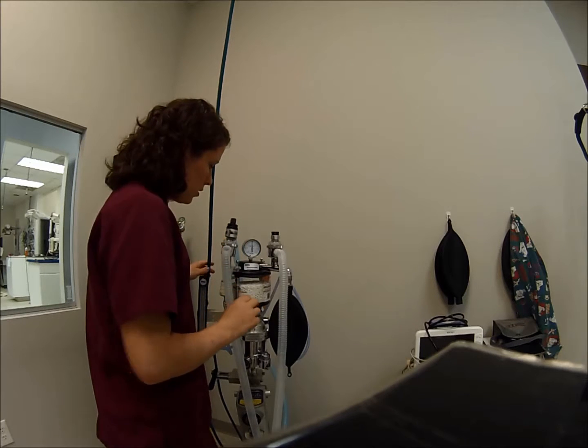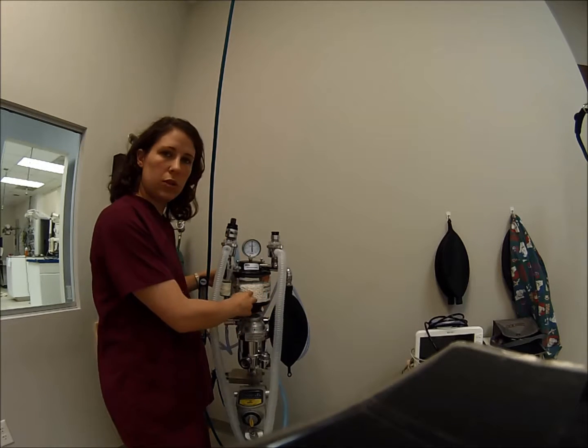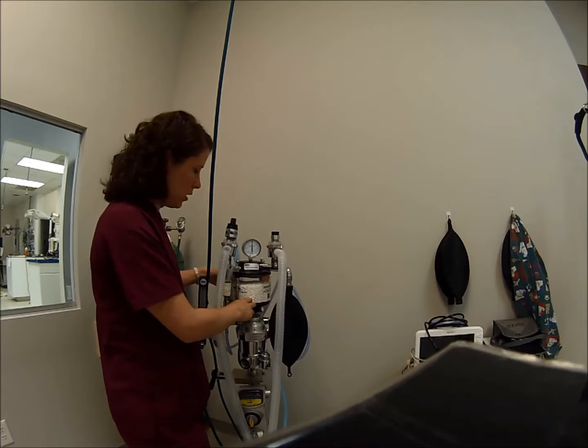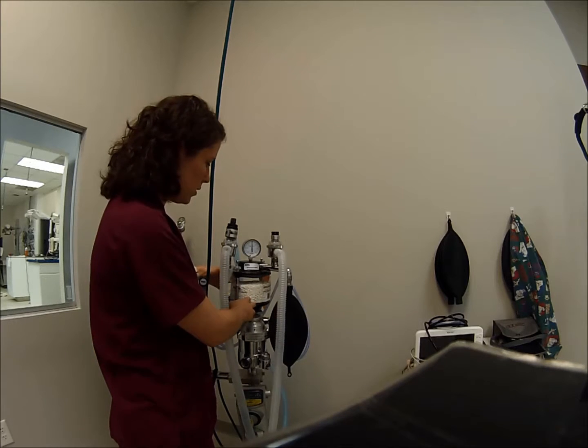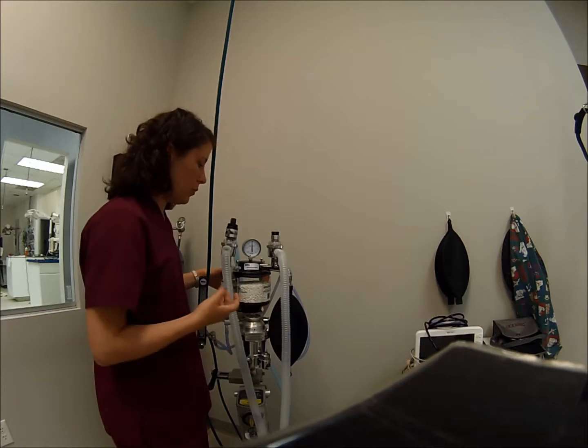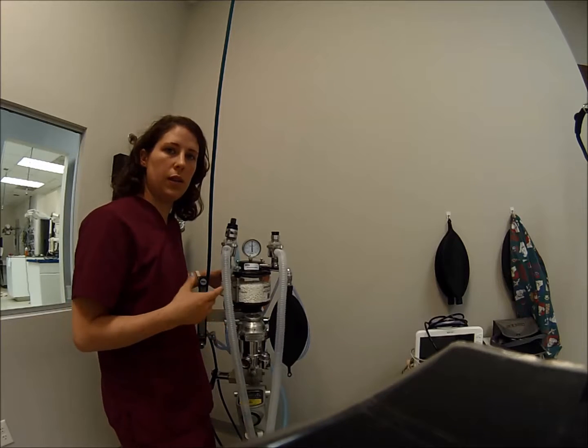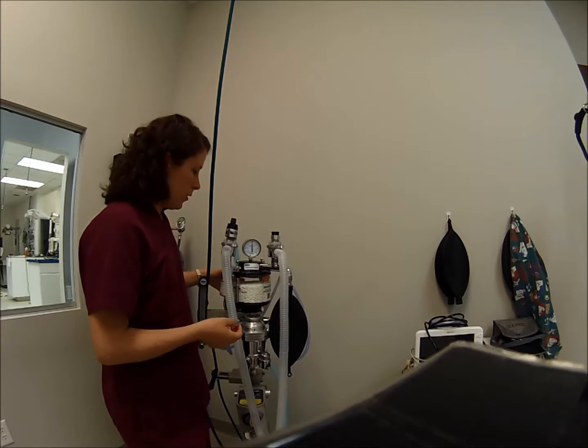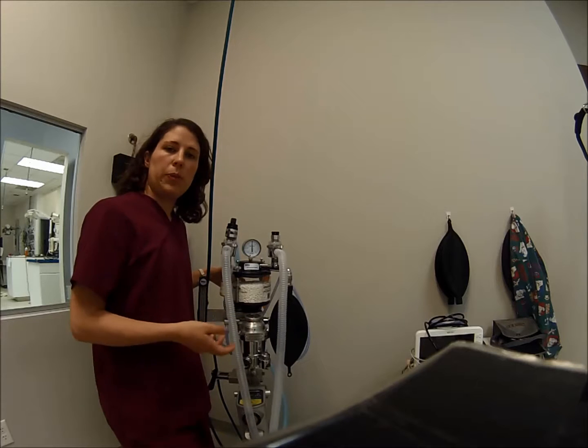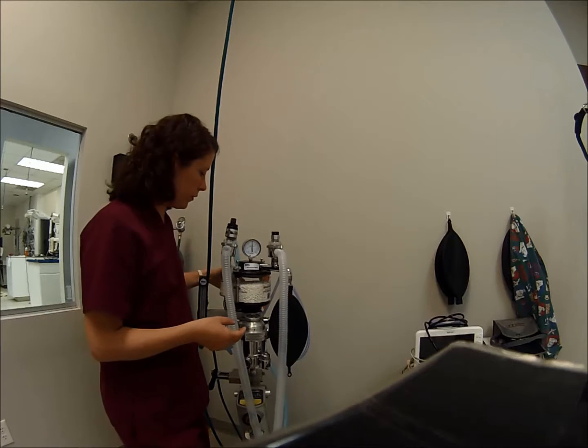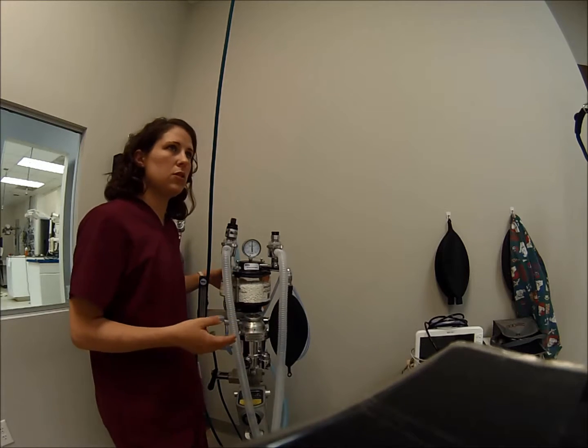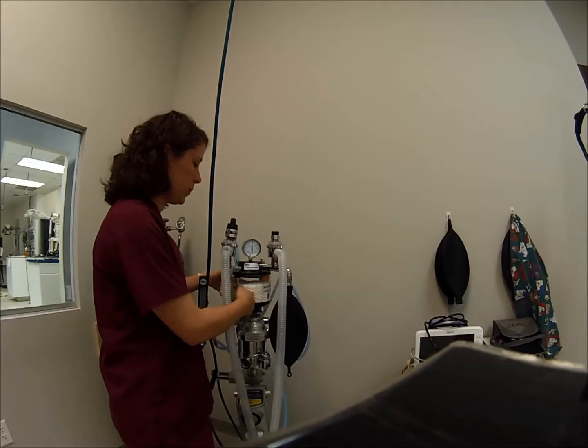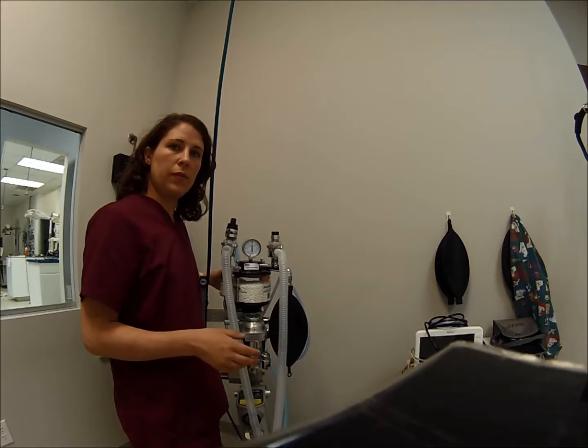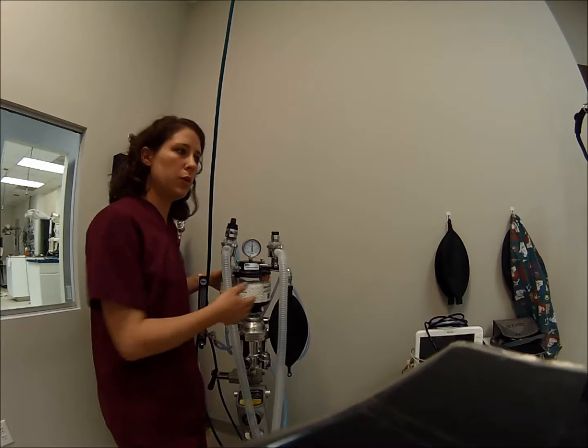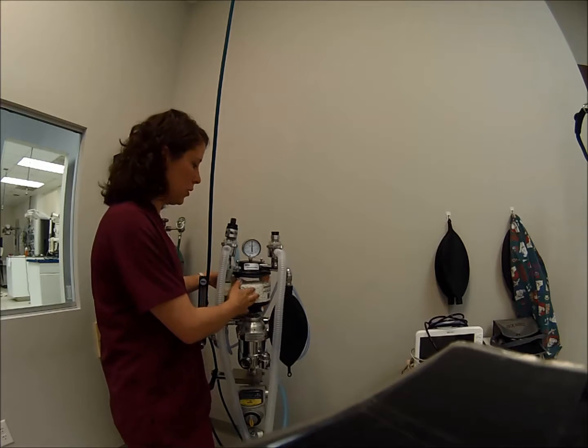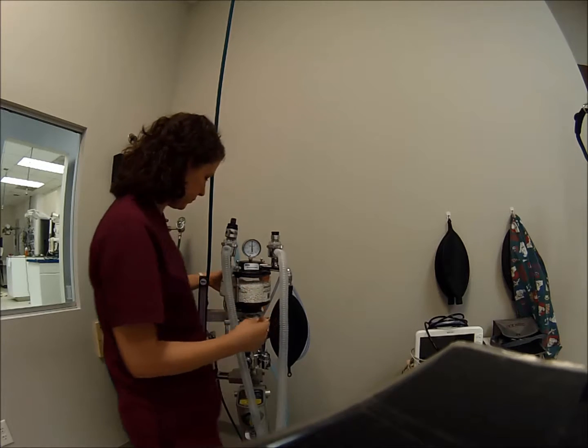The CO2 canister is here. This consists of granules that will absorb the CO2, and they create a reaction together. When the crystals are depleted, they turn a purple color. In that instance, you'll want to replace your crystals, but you never want to wait till it gets that far. You'll always want to have a maintenance schedule with this to replace the crystals.